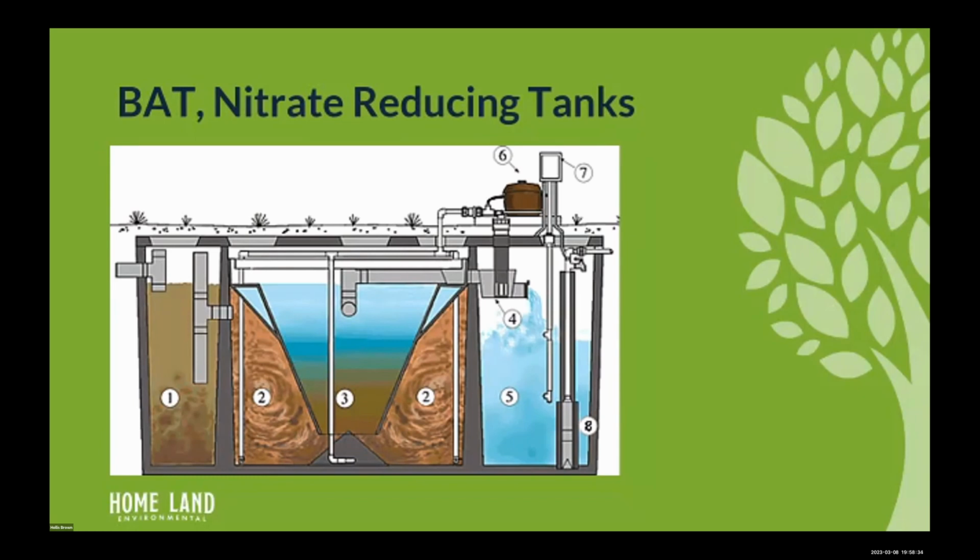The second chamber is where we start introducing oxygen. So there's a blower in almost every one of these. I think every one. Sometimes it sits right on top of the tank. Sometimes it's hidden closer to the house. But that blower, for the most part, 24/7 is blowing oxygen or air in this tank, and it's blowing up through here. So just making contact all the way up.